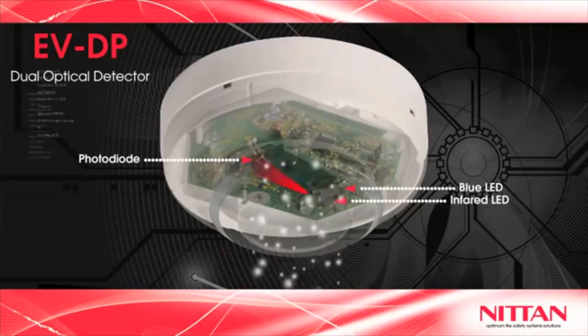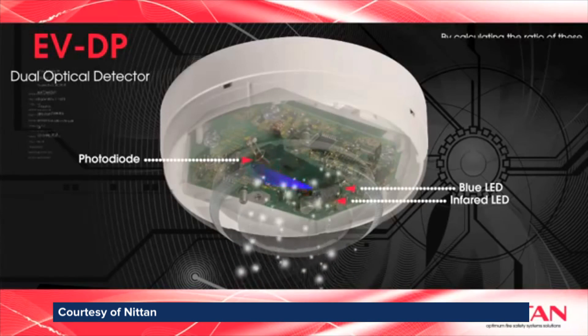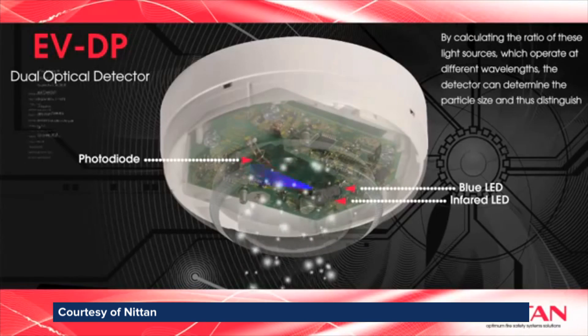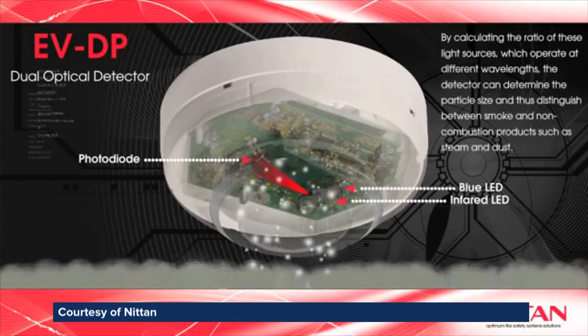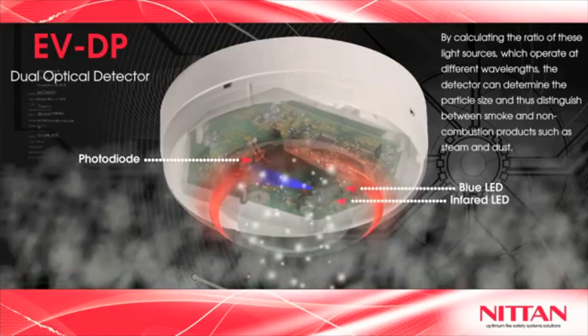We monitored it for 12 months, and during that period we've had zero false alarms. NITTAN's dual optical alarm doesn't just use standard infrared light — it also uses blue LEDs operating on different wavelengths. It can tell the difference between smoke and non-combustion products such as steam and dust.